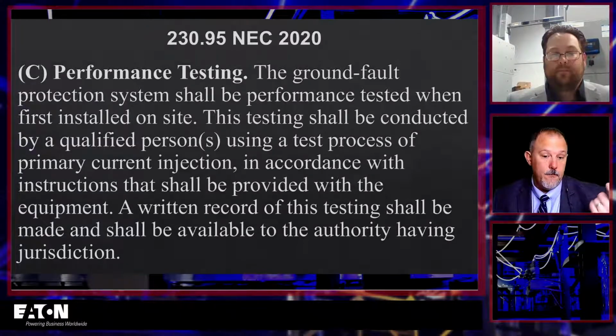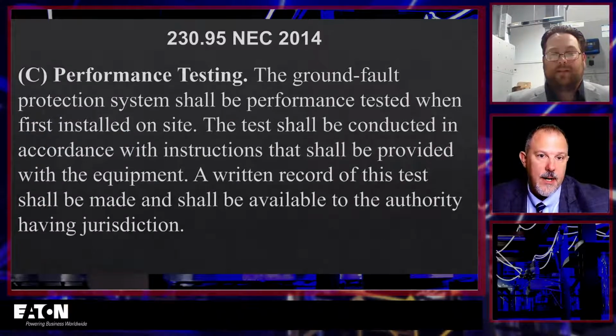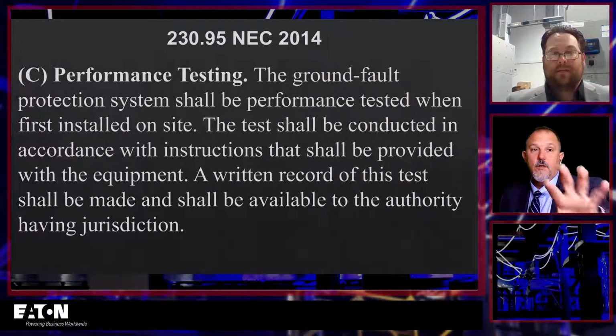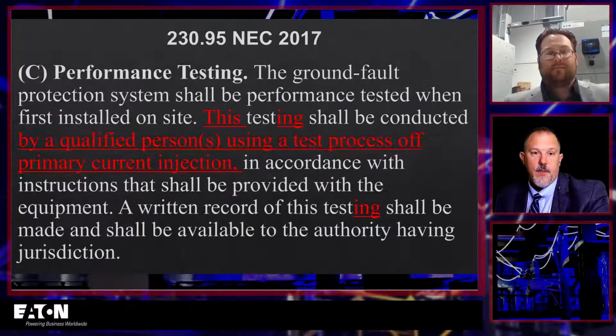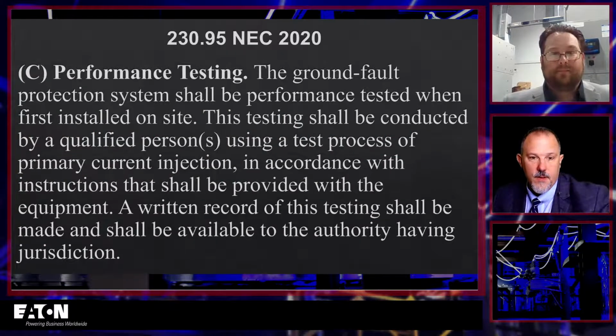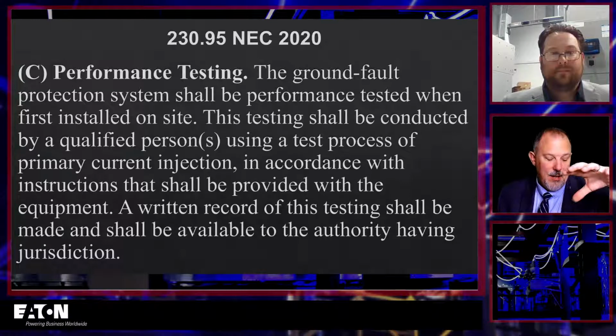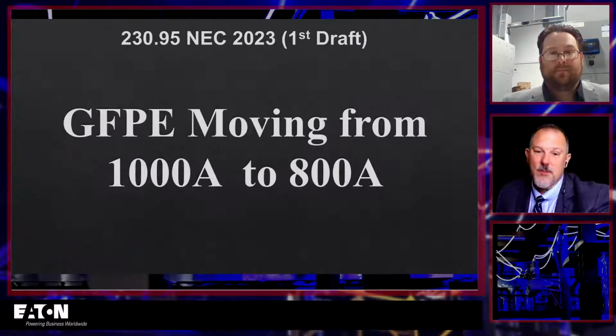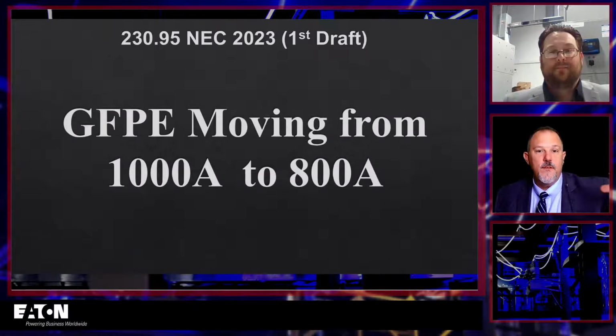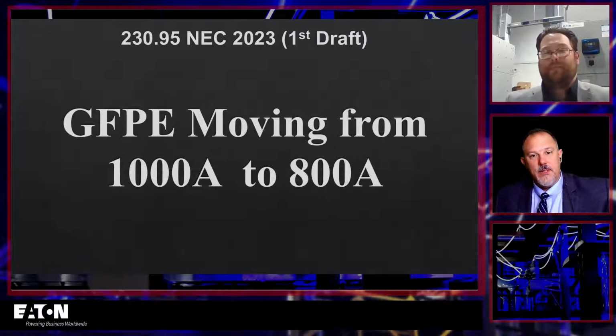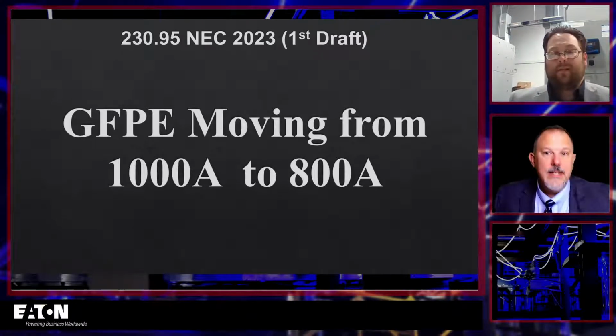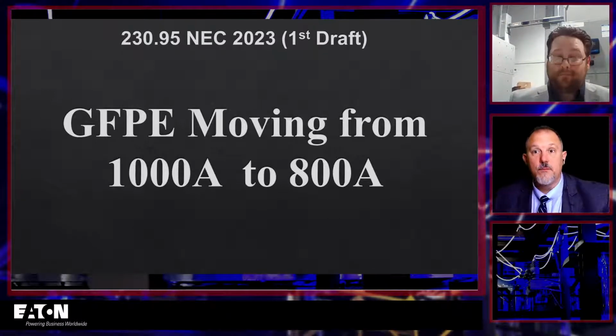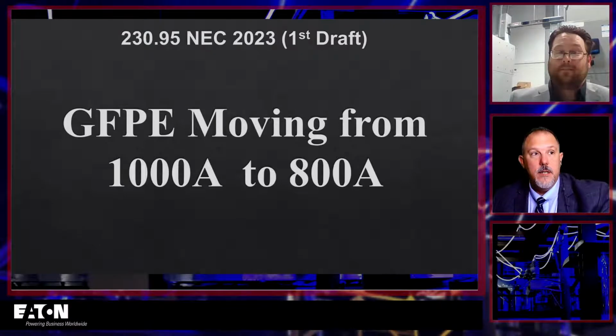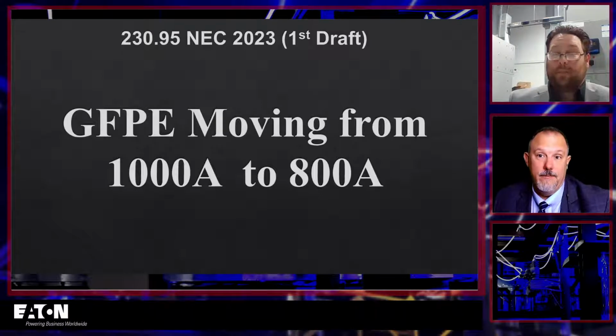But I'll tell you, I'm just giving you an example from the 2014 code, from the performance testing. They added primary current injection testing, and then the important thing is that in the 2023 cycle, this is what I was looking for, the thought process is that Panel 10 is going to take the 1,000 amps down to 800 amps, and this will be the first move that this section has seen since 1971.